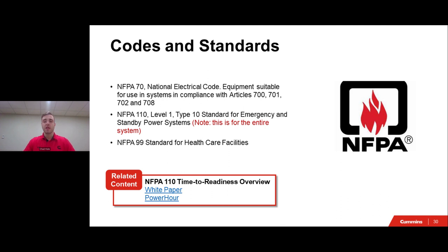And then lastly, we have NFPA 99 there down at the bottom. This is if you are a healthcare facility. This will help you understand all these special requirements that are needed for your power system within one of these applications. For example, you can need a bypass transfer switch, or you may need special annunciation. So to understand if you need one of those two things, take a deeper look into NFPA 99, as it also splits up your system into three different types. So if you need to understand what type your system is as defined by NFPA 99, you'll need to go ahead and look deeper into that code.